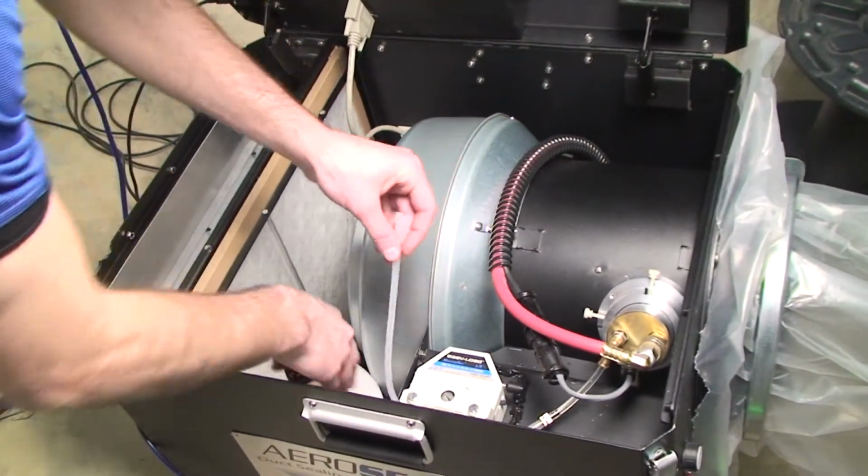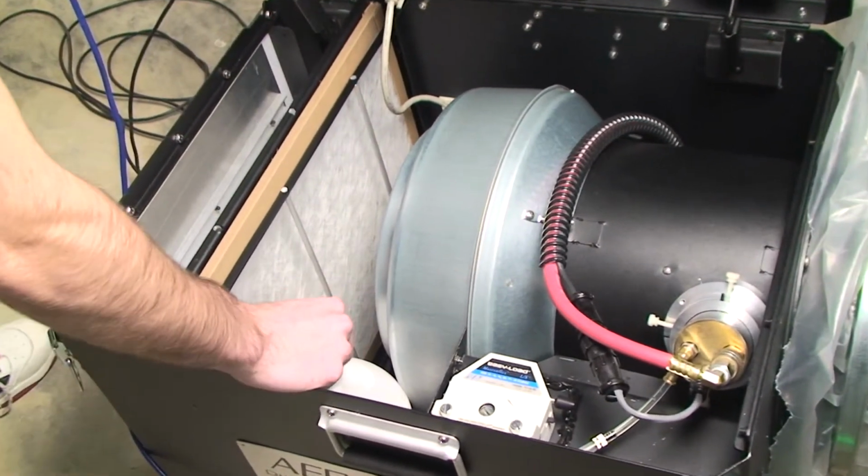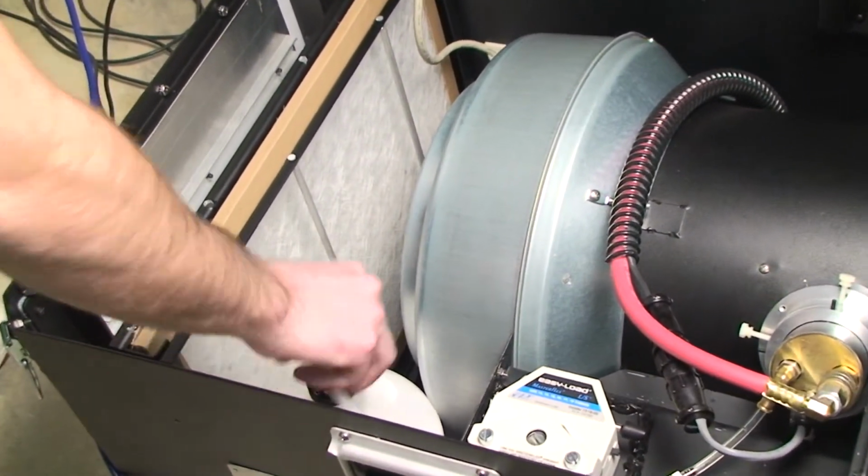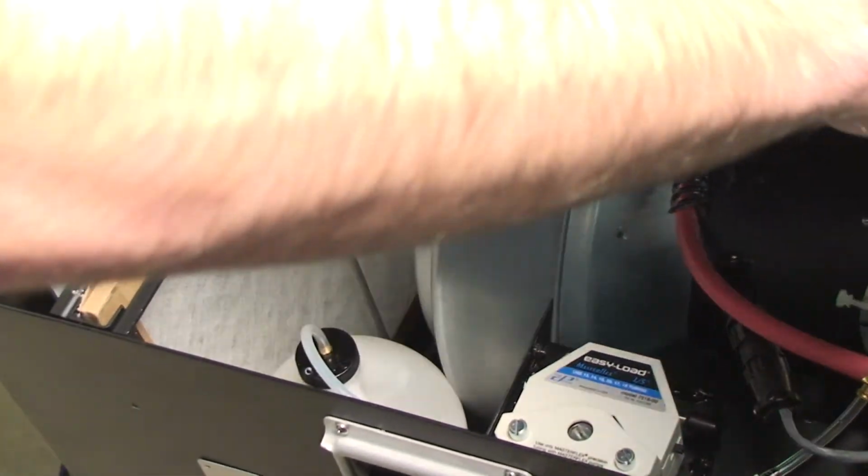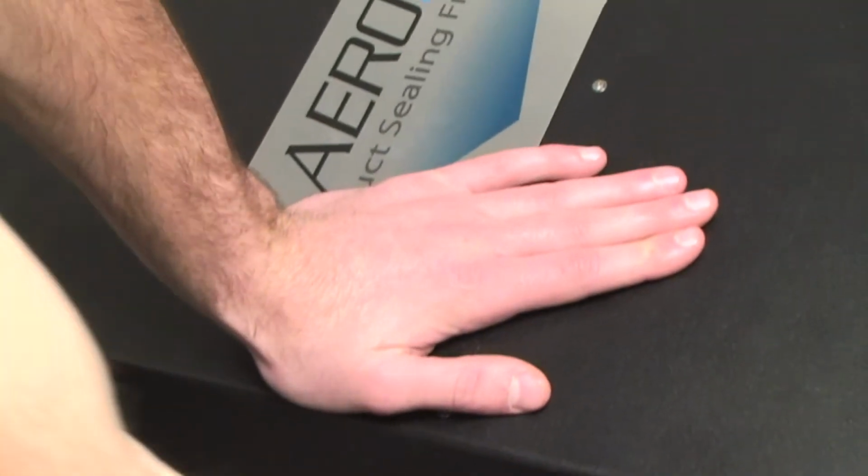My house, when I bought it, I knew was a 1980 vintage home and therefore had extremely leaky ducts. I didn't realize they were as leaky as they were. One of the only systems I thought would work for me was an aerosol-based injection system. My duct layout's very complicated and not accessible, so an aerosol injection system was a very good fit for me. And when we did it, we reduced the leakage from over 600 CFM down to about 80. So that's like an 80% reduction in leakage.